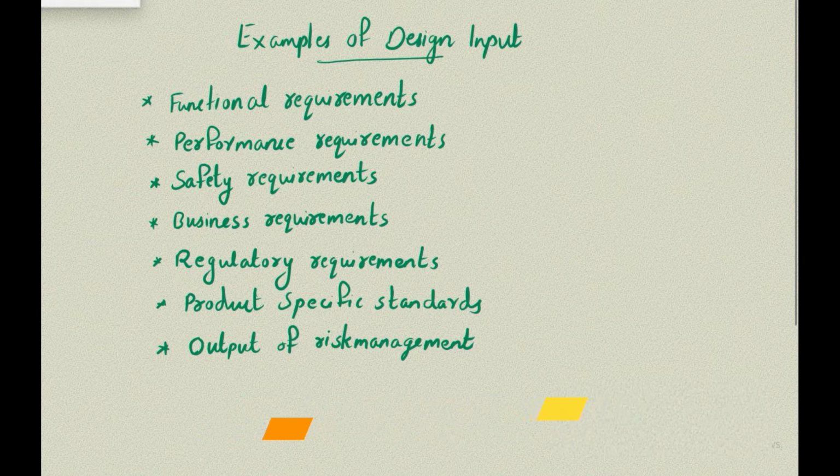So basically, we need to make sure that the requirements are complete, well defined, and not in conflict with each other. So when it is more clear, you will be able to march towards the end product easily without any confusion. And all the design input documents are to be properly documented, reviewed, and approved by the designated individuals.